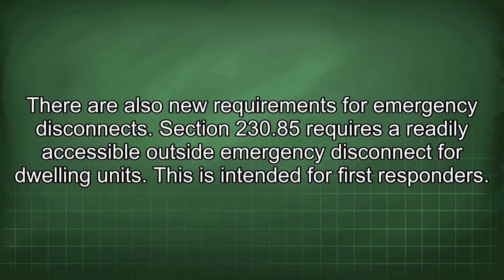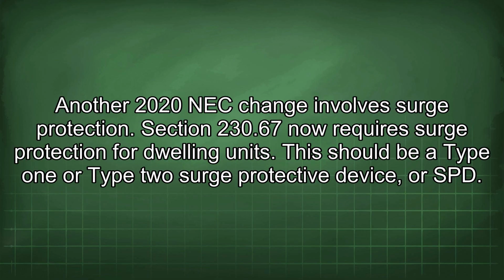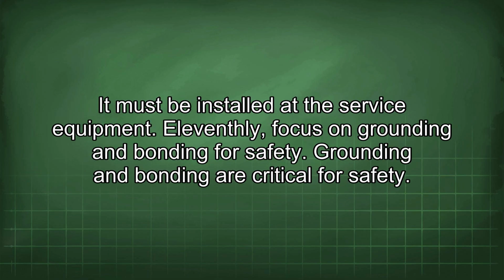There are also new requirements for emergency disconnects. Section 230.85 requires a readily accessible outside emergency disconnect for dwelling units. This is intended for first responders. Another 2020 NEC change involves surge protection. Section 230.67 now requires surge protection for dwelling units. This should be a Type 1 or Type 2 surge protective device, or SPD. It must be installed at the service equipment.